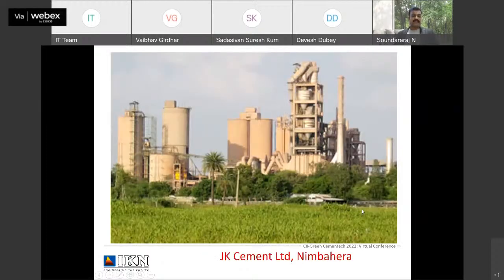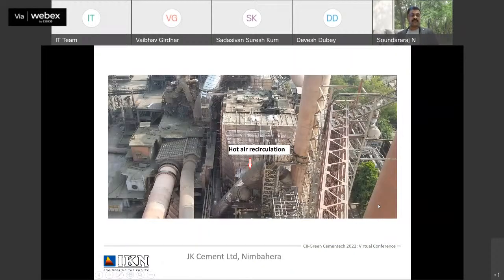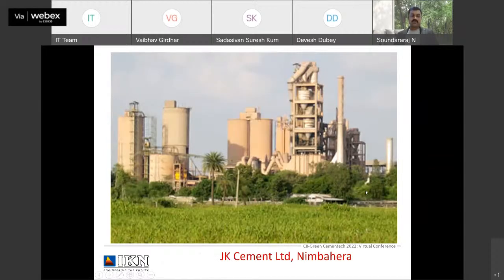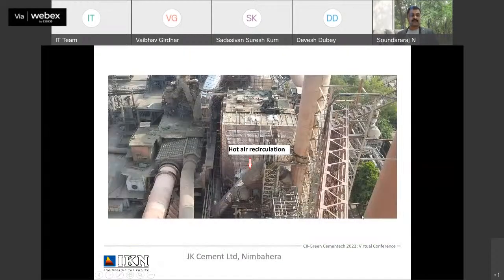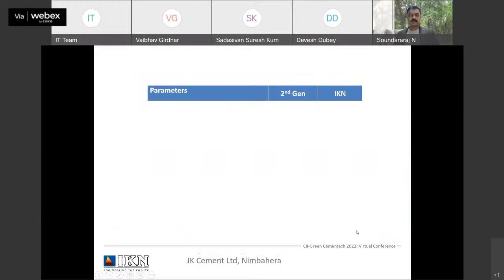In the case study, I'm going to share an interesting fact about the JK Nimbahera Line 3 IKN cooler. They had a conventional cooler with good WHRS generation. They decided to improve the recuperation, and to improve recuperation and reduce the clinker temperature, they wanted a new efficient cooler. When they approached IKN, we gave a solution with hot air recirculation to keep the WHRS performance without sacrificing fuel consumption. This is the JK Nimbahera cooler, and you can see the hot air duct from the cooler stack at 120 degrees recirculated to the selective cooling fans in the mid zone. How did the cooler modification with HAR benefit them?